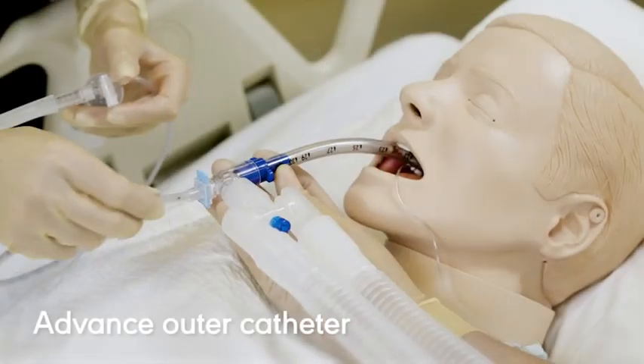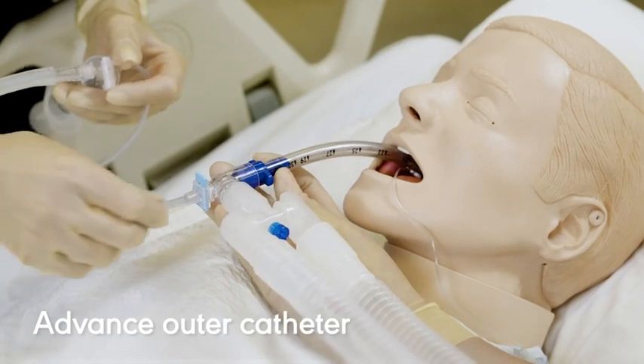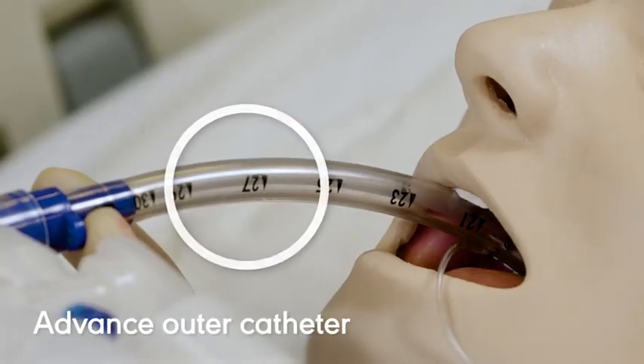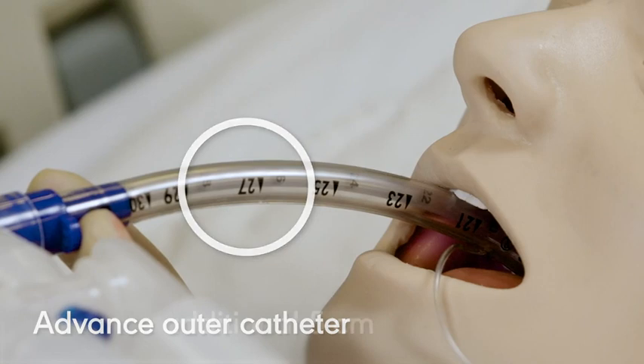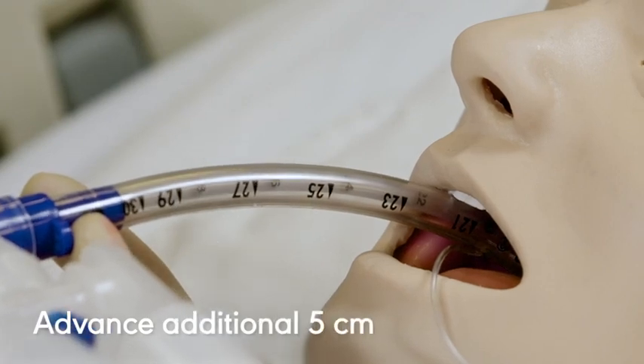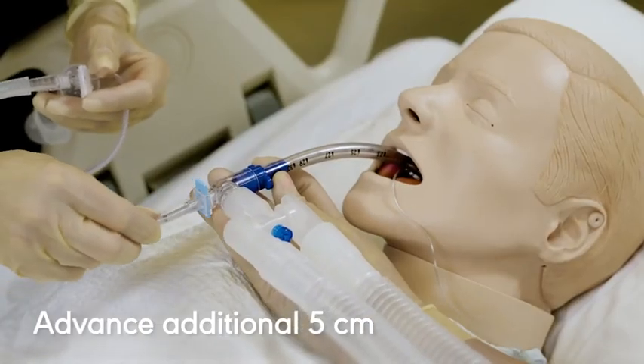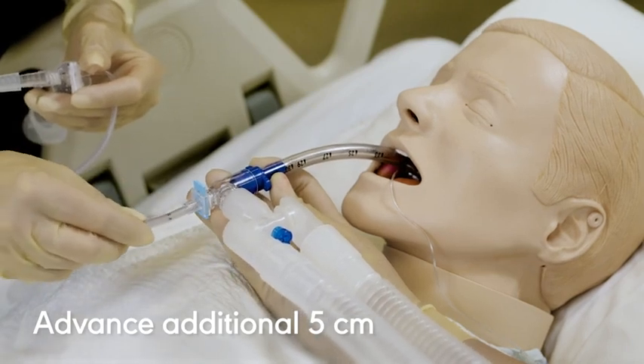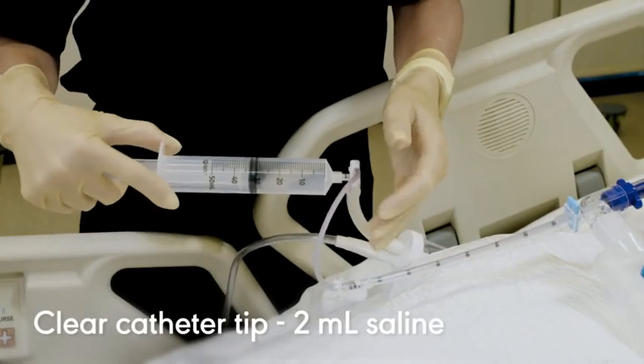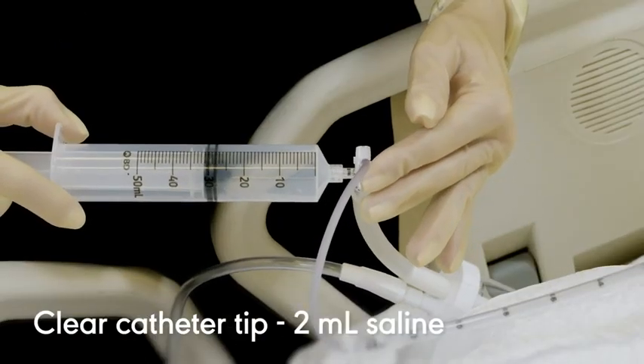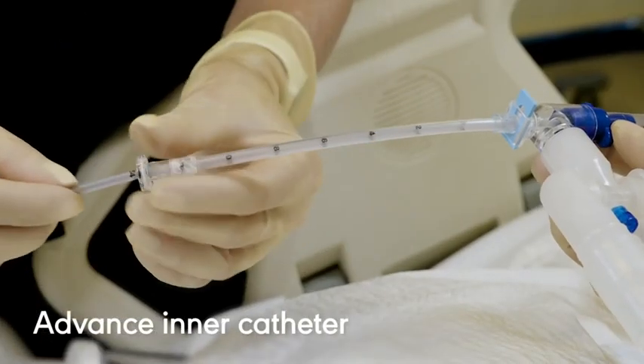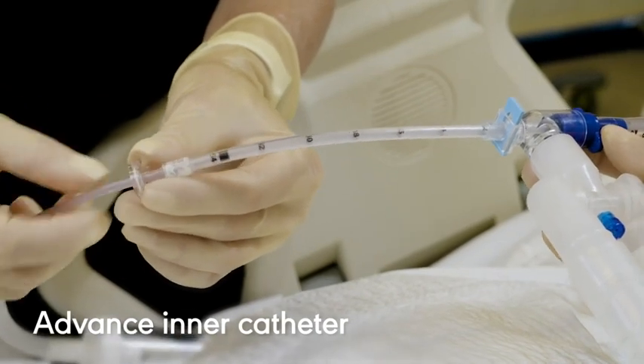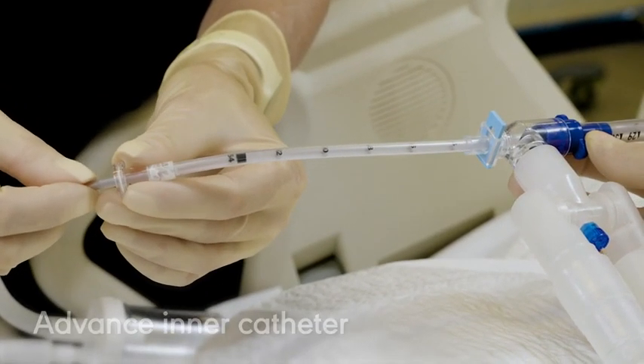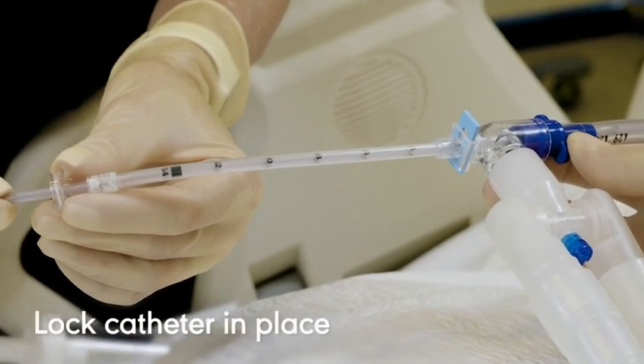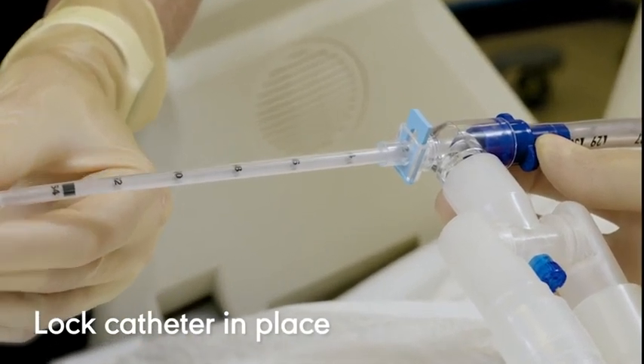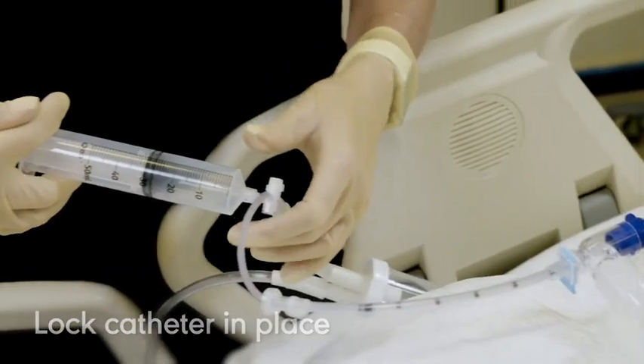Advance the outer catheter of the mini-BAL until the markings on the catheter match up with the number on the ET tube, and then advance another 5 centimeters so the catheter is positioned on the left or right main stem of the bronchus. Clear the tip of the catheter by instilling 2 milliliters of saline through the catheter. Hold the outer catheter in place and advance the inner catheter until resistance is met, and then pull back slightly. Lock the catheter in place by pushing the blue slide lock on the elbow adapter downward.